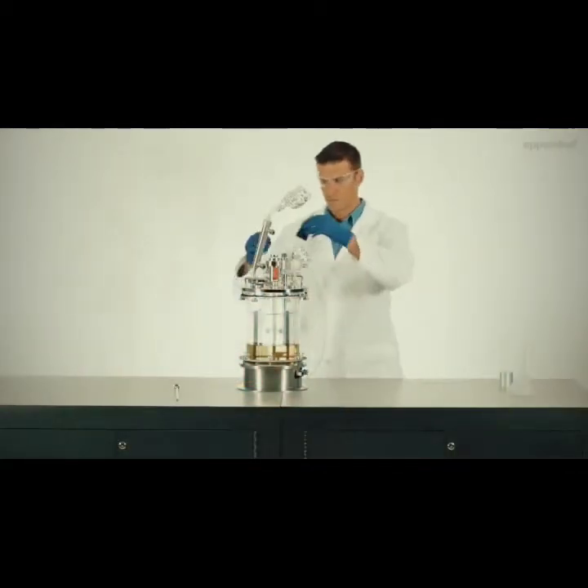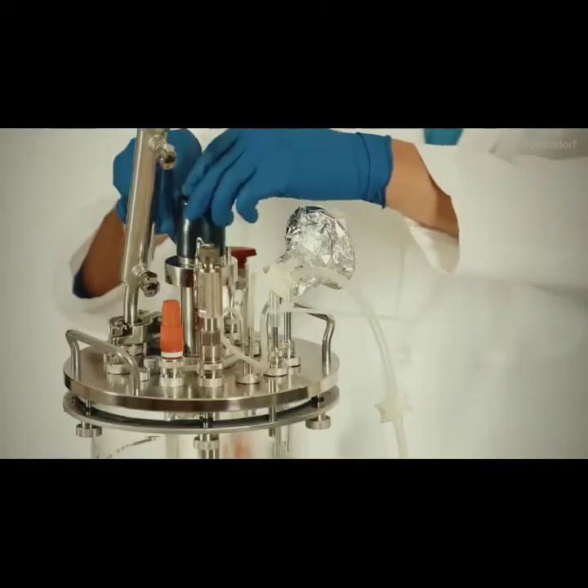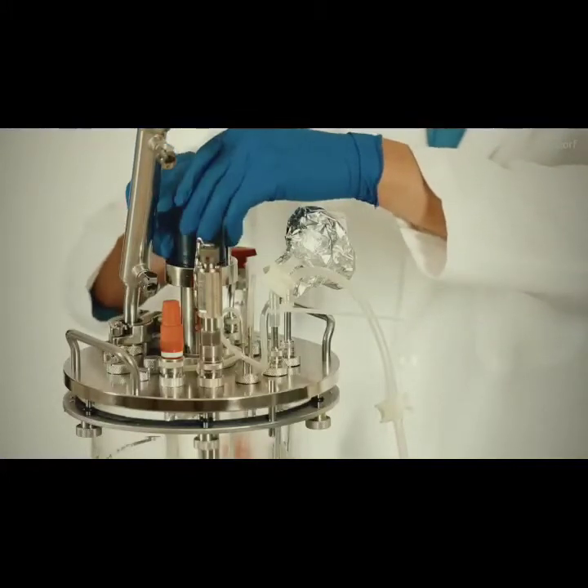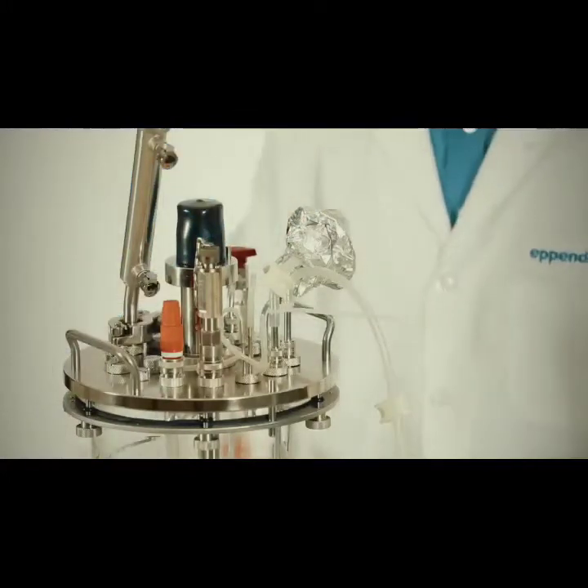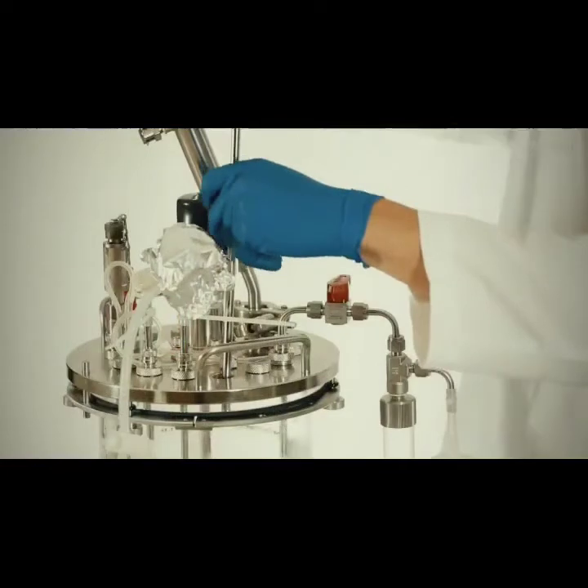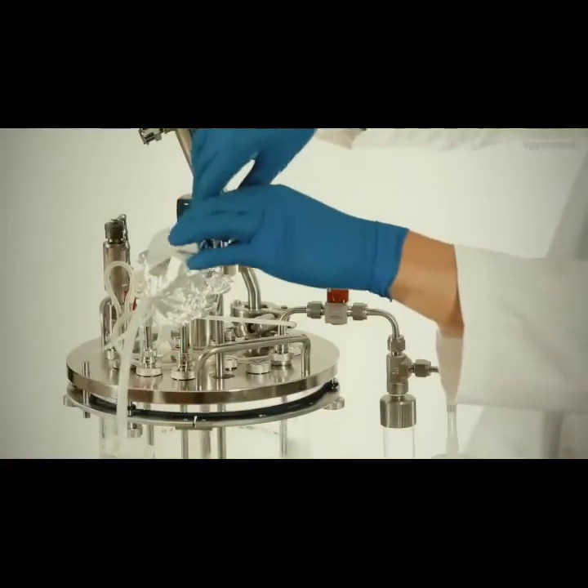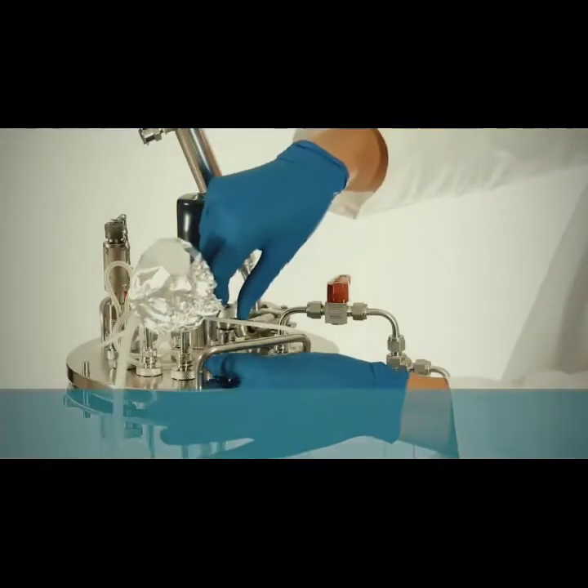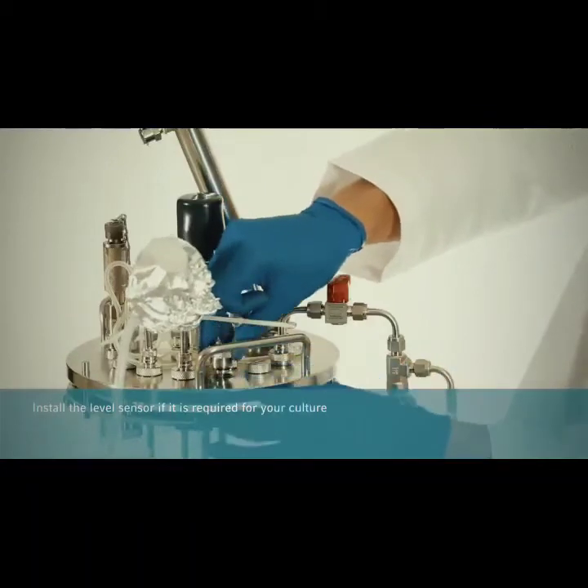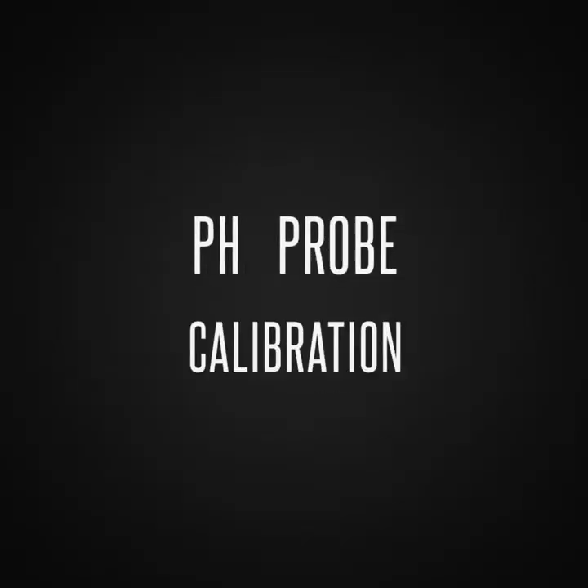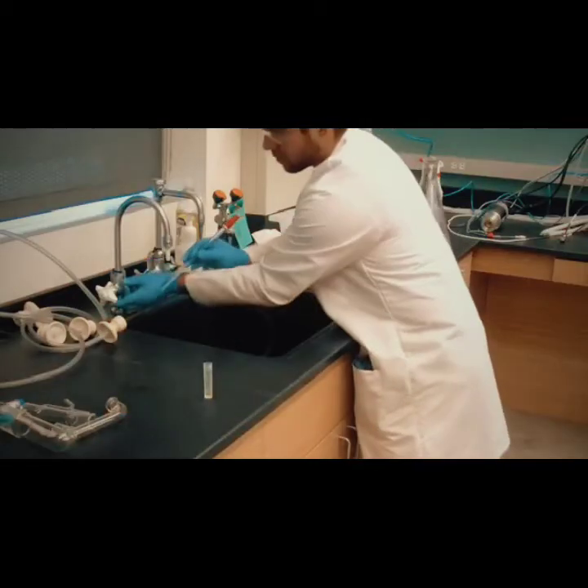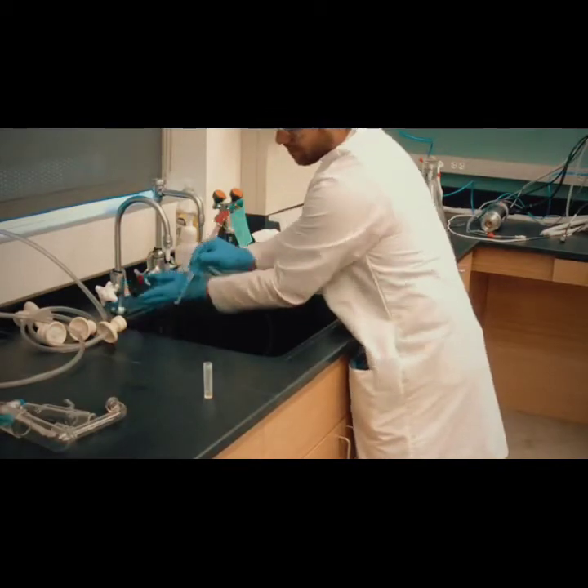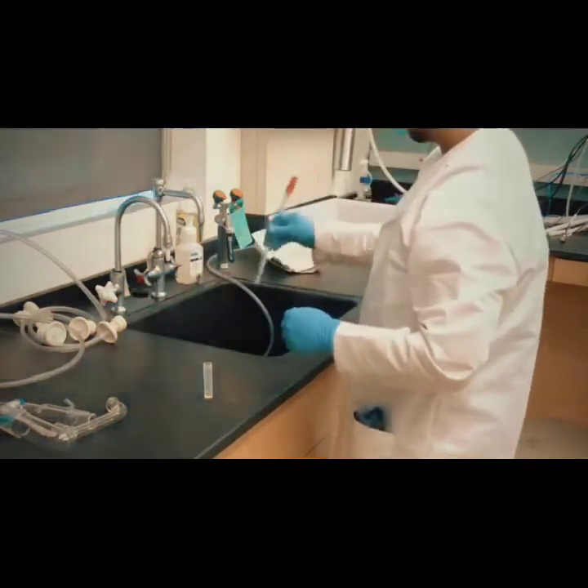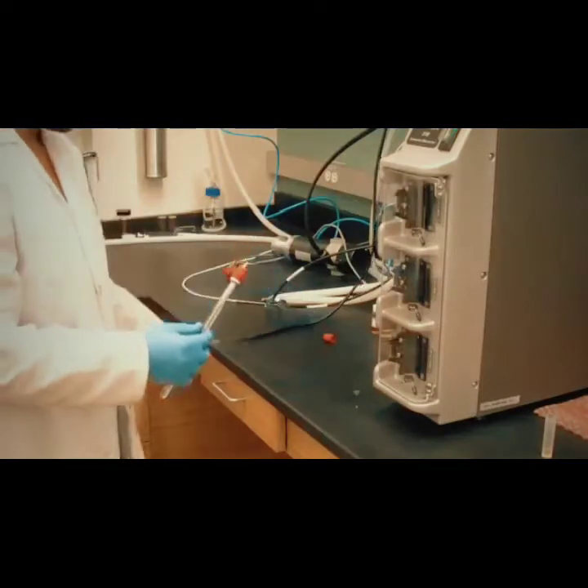Place a cap on the bearing housing to protect it from any potential damage during the autoclave cycle. Insert the thermowell. Install the level sensor if it's required for your culture. Remove the probe from the 4 molar potassium chloride storage bottle and rinse with distilled water. Connect the probe to the PCU with the cable.